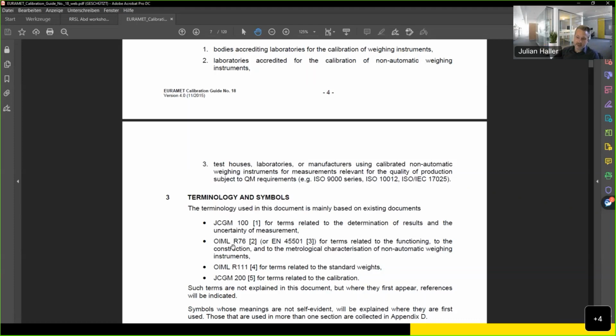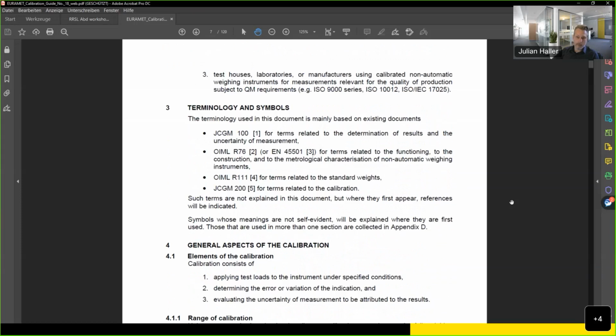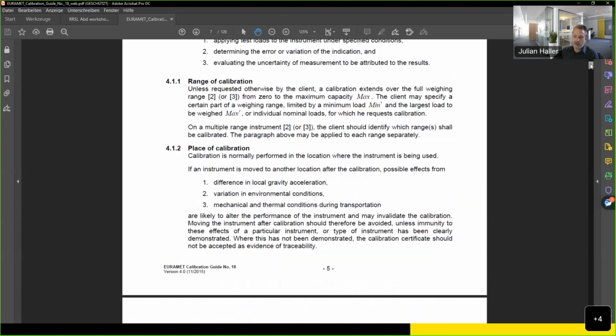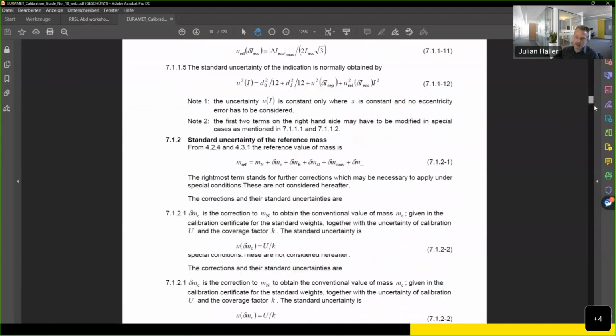You see, R76 is mentioned here as a reference for terminology, for example, but it is really different. And what is sometimes a bit unfortunate is that the measurement procedures themselves are not directly comparable. A very simple example is repeatability. According to cg-18, you have to zero between each repetition, between each loading, and that makes a difference. And you calculate the standard deviation, while R76 determines the difference between the minimum and the maximum of the repetitions. So these documents are really hard to compare. I personally recommend to calibrate according to cg-18 and to test in legal metrology according to R76.